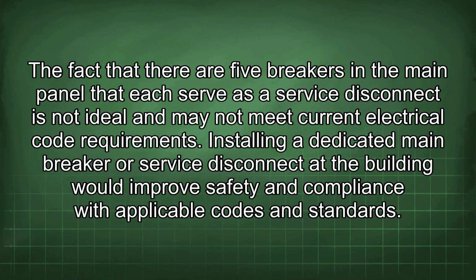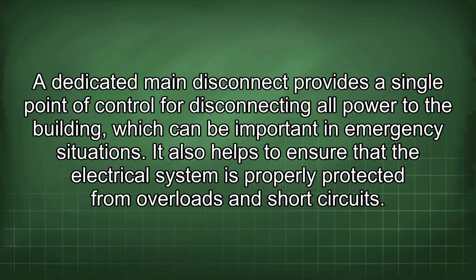Installing a dedicated main breaker or service disconnect at the building would improve safety and compliance with applicable codes and standards. A dedicated main disconnect provides a single point of control for disconnecting all power to the building, which can be important in emergency situations. It also helps to ensure that the electrical system is properly protected from overloads and short circuits.